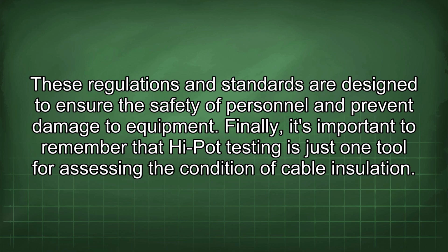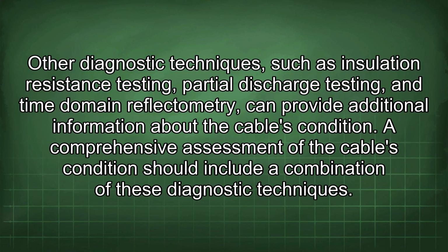Finally, it's important to remember that high-pot testing is just one tool for assessing the condition of cable insulation. Other diagnostic techniques such as insulation resistance testing, partial discharge testing, and time domain reflectometry can provide additional information about the cable's condition. A comprehensive assessment of the cable's condition should include a combination of these diagnostic techniques.